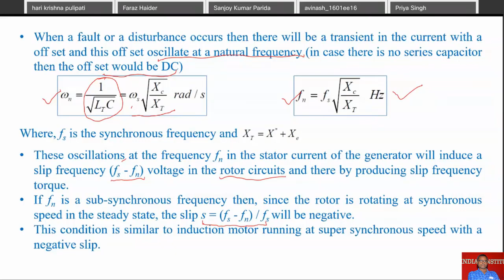That will be negative because from this expression we can see that Fn is greater than Fs, because when we multiply by root Xc by Xt, obviously it will give a value greater than Fs. So therefore S will become negative. So when the slip becomes negative, what is the condition? This condition is similar to the induction motor running at super synchronous speed. That is nothing but it will work as the induction generator with the negative slip, right?